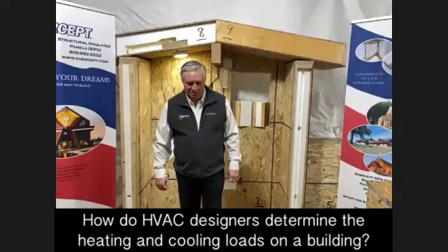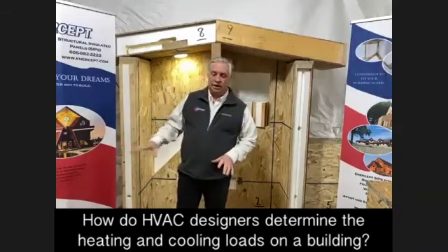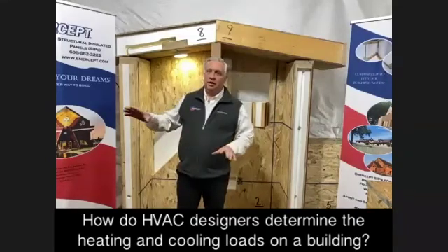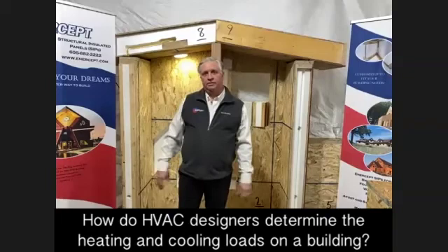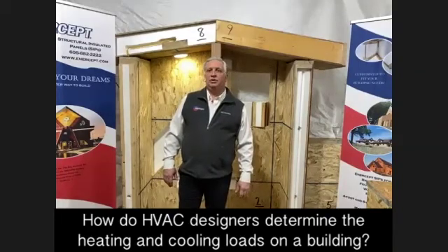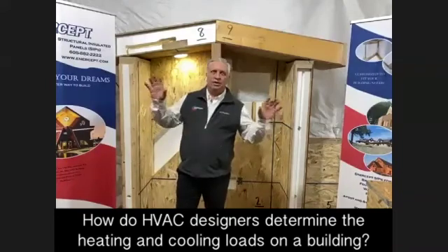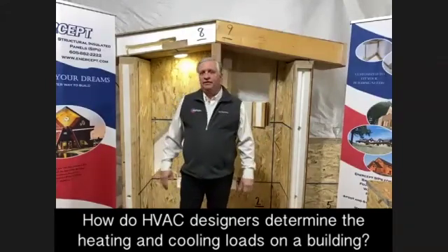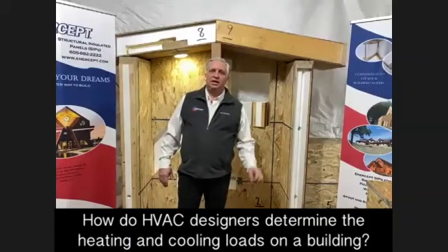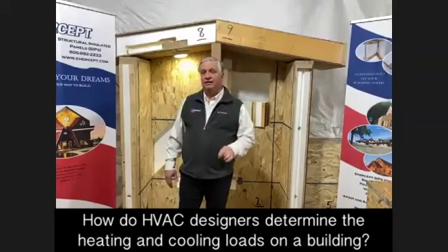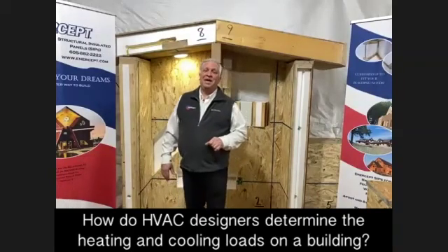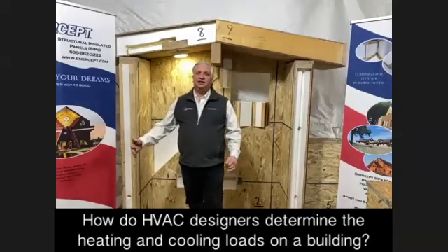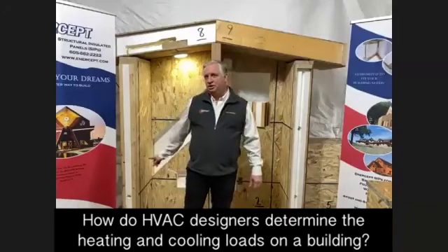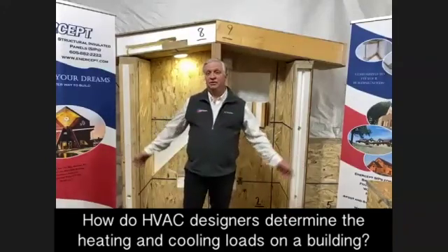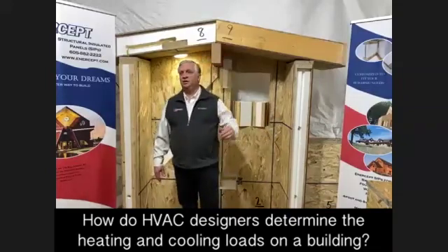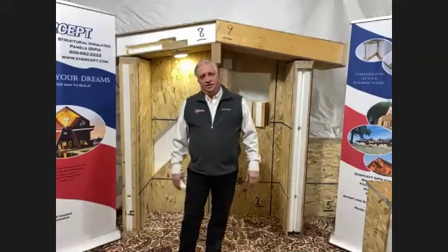And it was interesting, I was talking to one pro. He was doing a computerized Manual J, and he started out by showing 2x6 walls, R19 fiberglass insulation, and his program showed 0.5 at resting, not pressurized, just at resting, 0.5 air exchanges per hour. And when he changed it to SIPs, the program automatically changed it to 0.05 air exchanges per hour resting. And he said that in itself knocked the size of that system down 20%. Just that one change in air infiltration, not taking into account R value, not taking into account thermal bridging, just air infiltration.